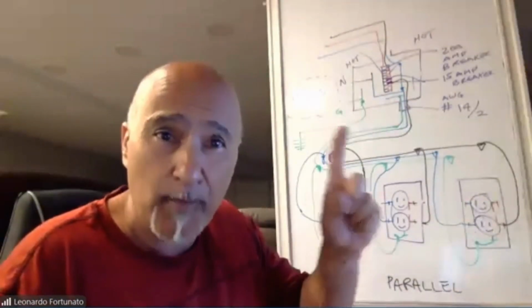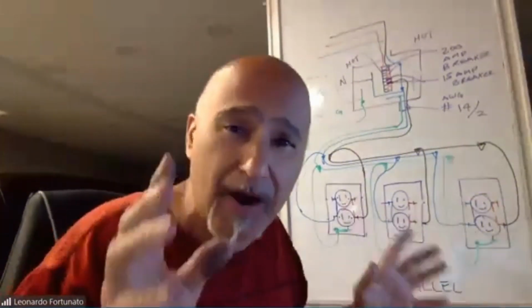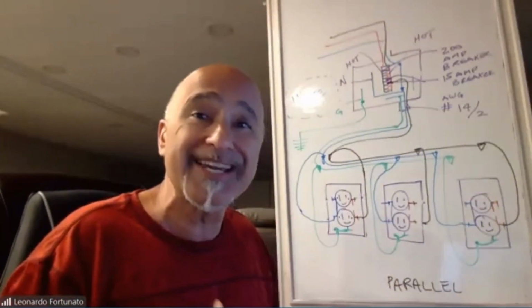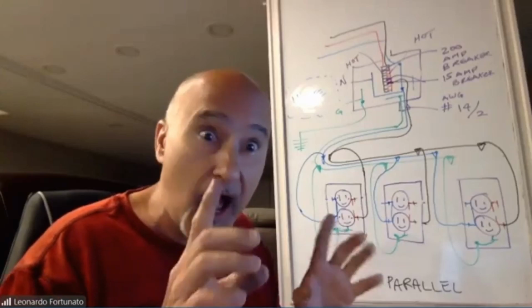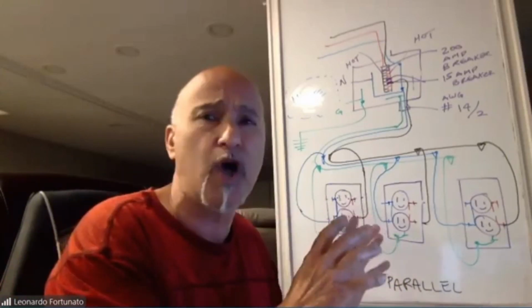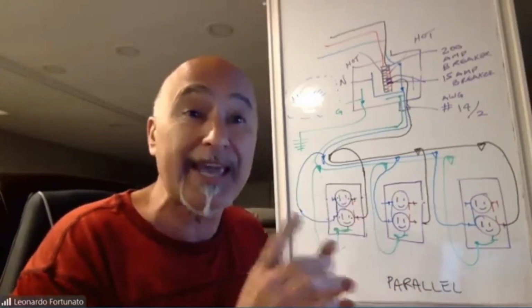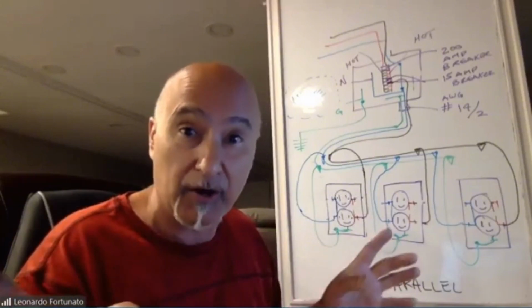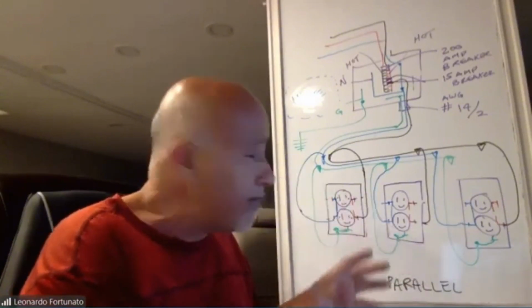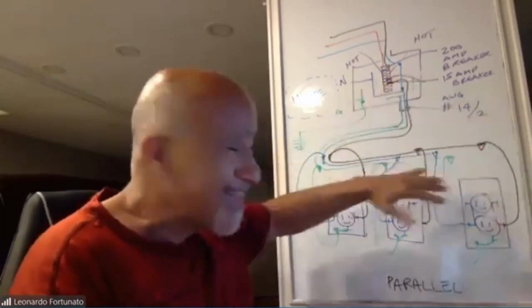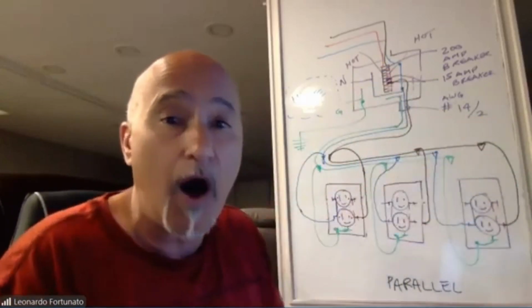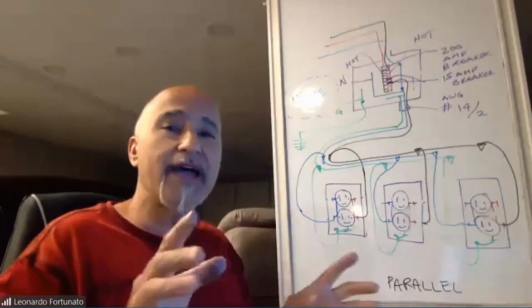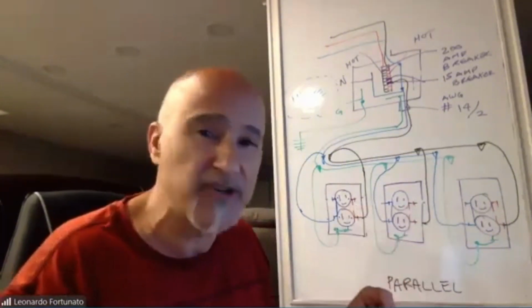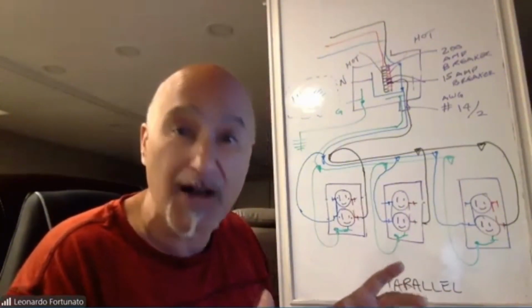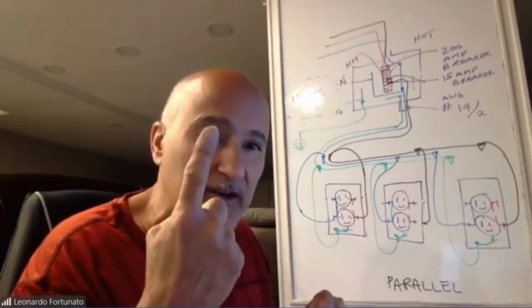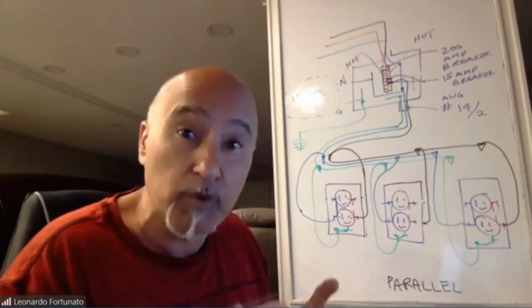Godwin is saying we need one more conductor, but if we are working in a residential environment, we are using cable. We're not using single conductor wire. Remember, in this case, because we're talking about residential, we're using cable. So if I'm using cable now, what would I need to do to bring that other conductor to all of these receptacles? Again, remember, we are talking about residential. Unless we are running conduit, we can't run a single conductor. We have to run cable.